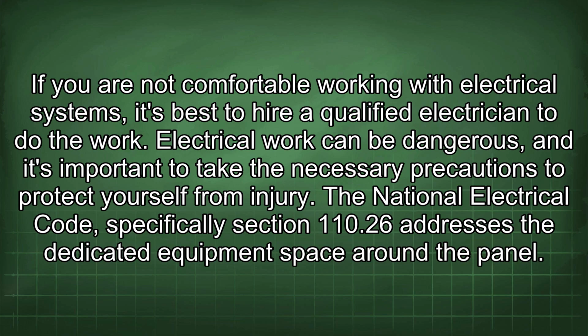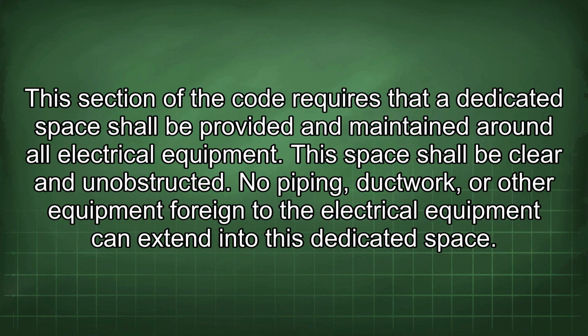The National Electrical Code, specifically Section 110.26, addresses the dedicated equipment space around the panel. This section of the code requires that a dedicated space shall be provided and maintained around all electrical equipment. This space shall be clear and unobstructed. No piping, ductwork, or other equipment foreign to the electrical equipment can extend into this dedicated space.